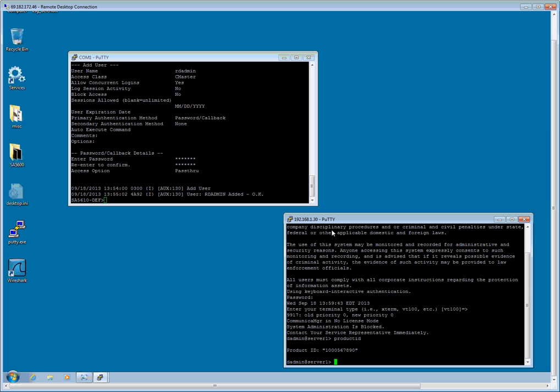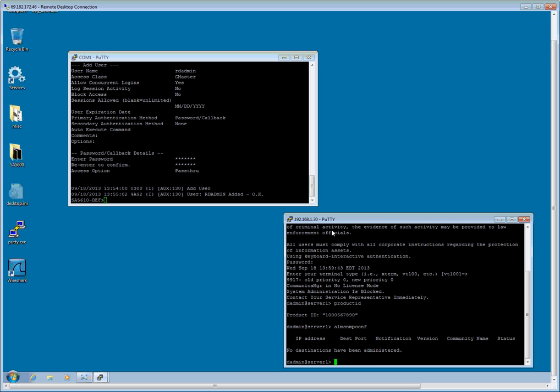Yep, our product ID is just as we entered it in the user name, which is 1-0-0-0-5-6-7-8-9-0. Now I am going to take a look at the INADS trap destinations. The command I am going to issue is ALM SNMP CONF. And I will hit enter. And as we see, there are no destinations assigned. So we are going to go ahead and enter the IP address and the community string of the SA5600 that we just configured.